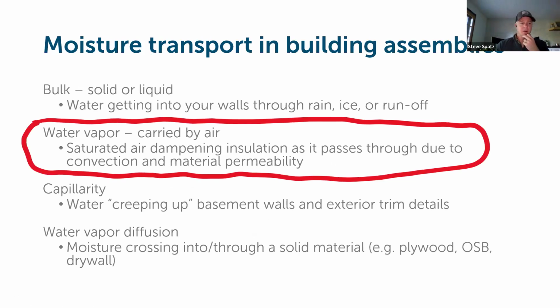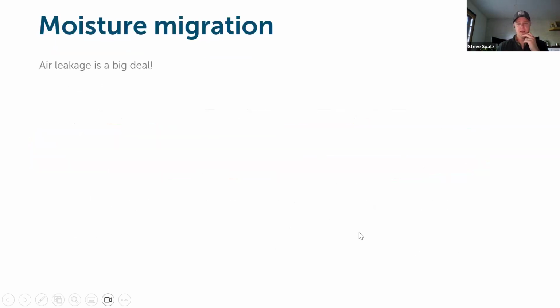The primary thing that we're avoiding against and mitigating against here with good vapor control inside the building, as far as a vapor control layer, and then also by good mechanical ventilation, is preventing the transport of moisture, water vapor moving through air. And that is why you have different transport mechanisms for moisture that can get into assemblies. You have capillary action, where you have wicking essentially from wet to dry that can transport moisture. Vapor diffusion, you have moisture vapor that will diffuse and move just kind of through pressure differential through materials. But the bulk of water can be carried if you have air movement through assemblies. And that's why it's critical when you're detailing air barrier and vapor control layers to make them as airtight as possible.